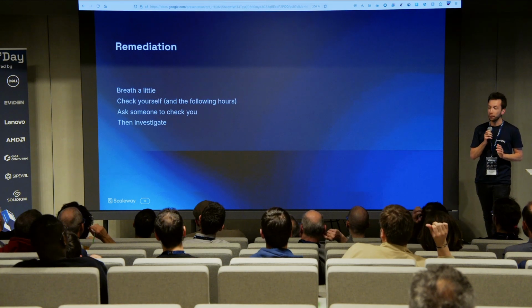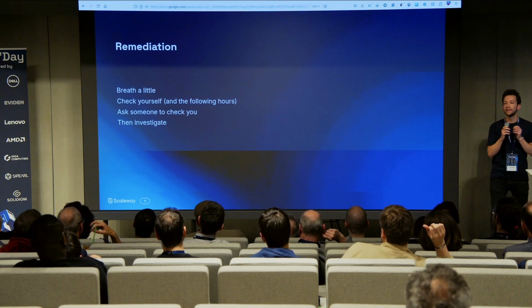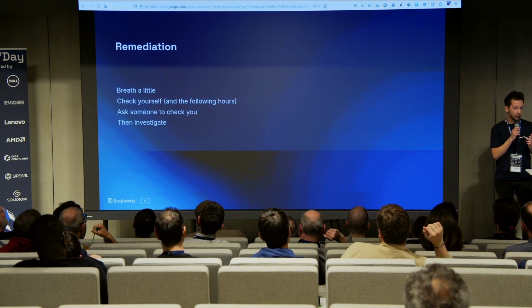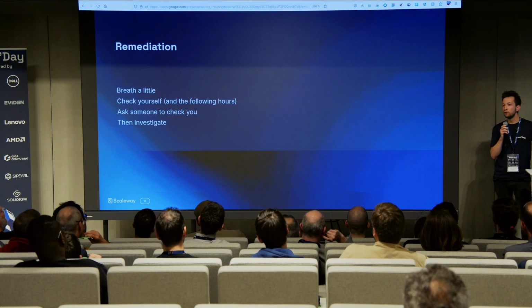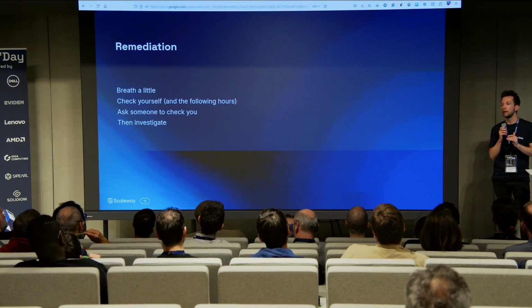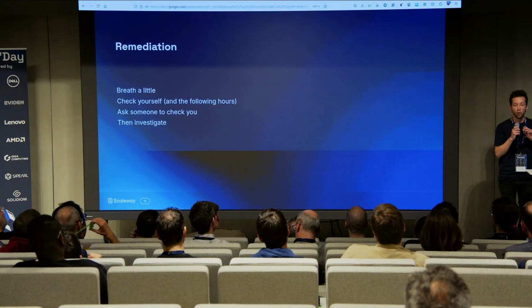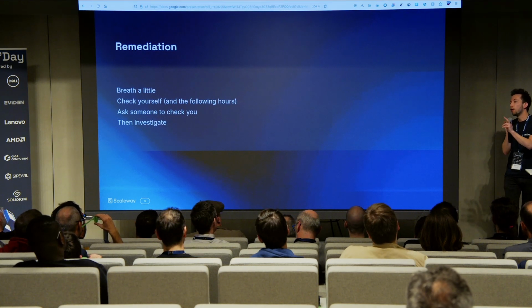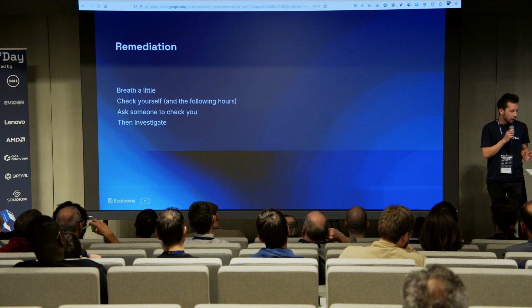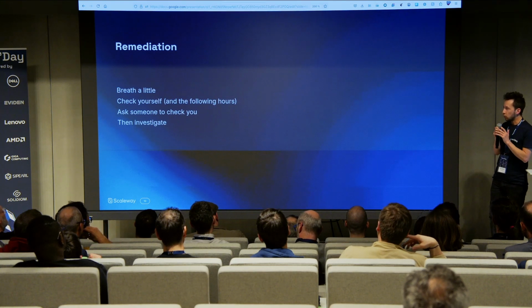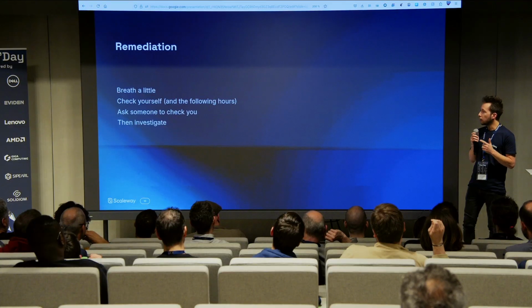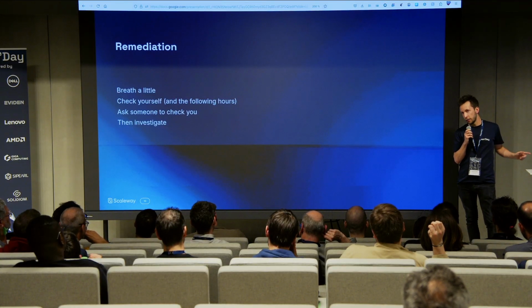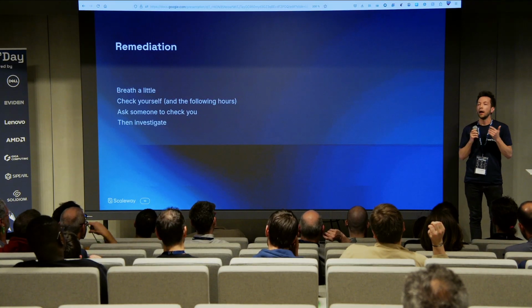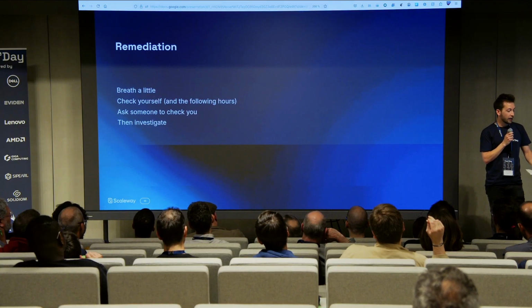So, for me, after investigation, it was not really dangerous in the end. There's no phase-to-phase contact, no phase-to-neutral, just inductive currents between one Earth and the other floating Earth. But at first you don't know what happened, so check yourself, ask someone to check you during the following hours. Then you can start to investigate. I hope nothing happened to you.